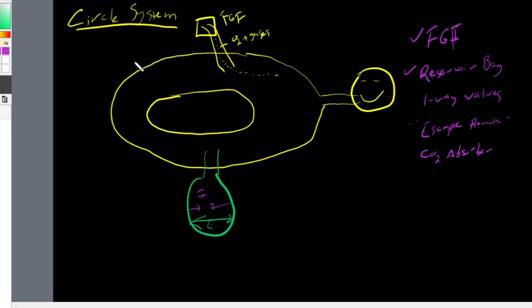Now, if you take a look, if we draw this circle here, this circuit of our circle system, we have gases coming in this way. But also, our fresh gas flow can also escape this way as well. When we exhale, we can exhale carbon dioxide this way. But we can also exhale carbon dioxide this way. That makes for a really inefficient mixed circuit. We need to have a way to provide some sort of unidirectionality to our circuit. And this is where our one-way valves come in. So we usually put a one-way valve here on the inspiratory side. Inspiratory valve. And we'll put a valve on this side of the circle system, which is going to be our expiratory valve.